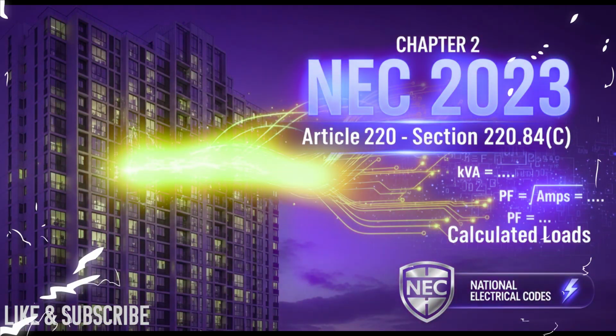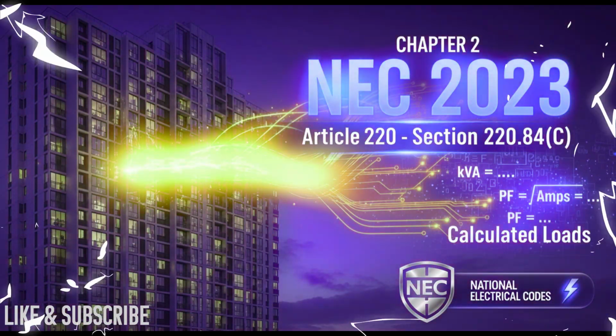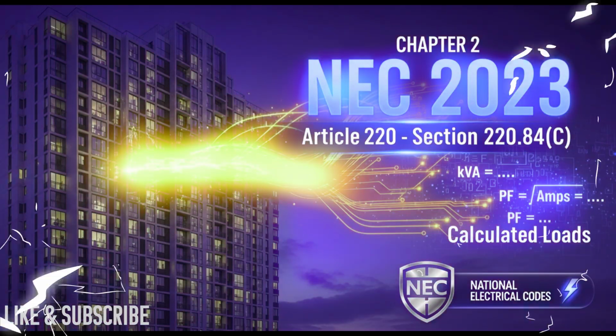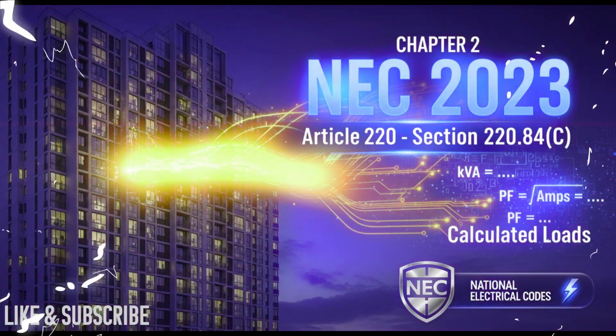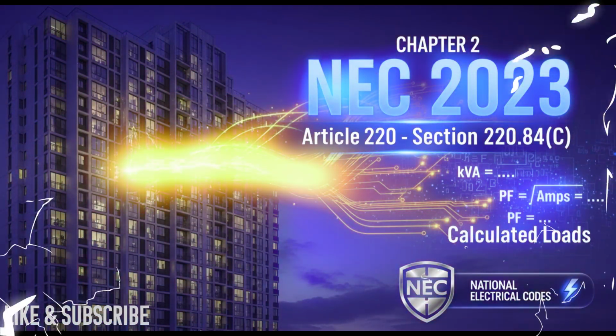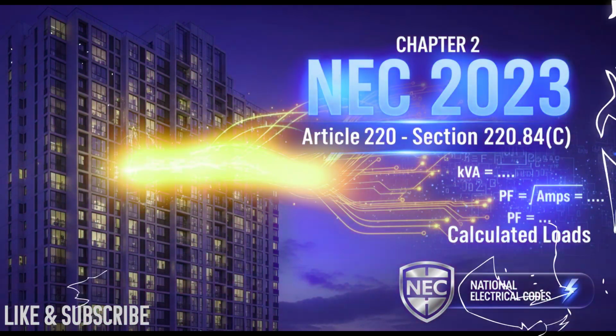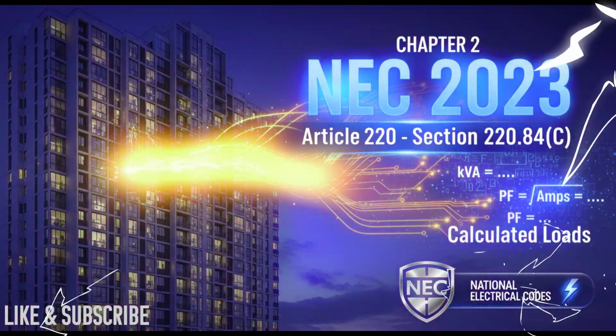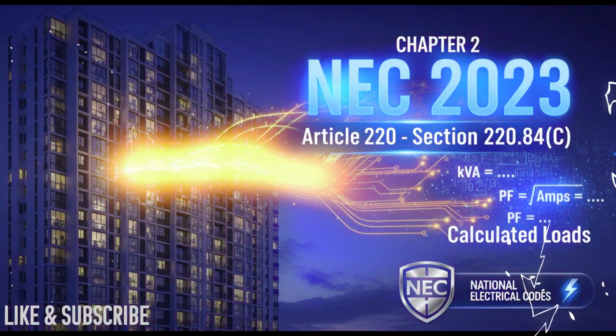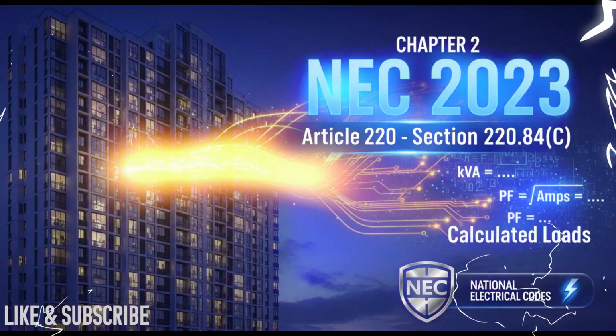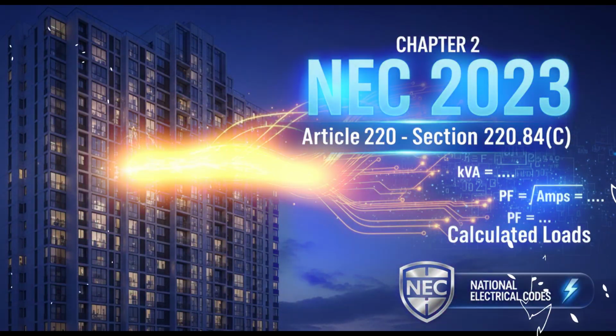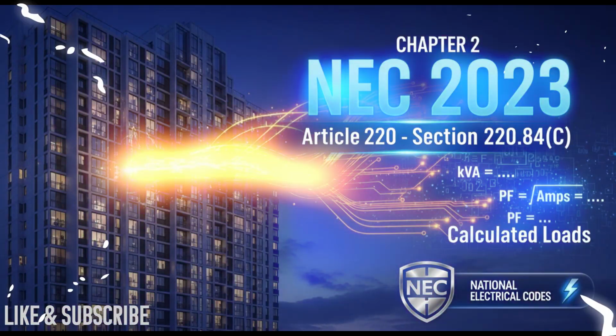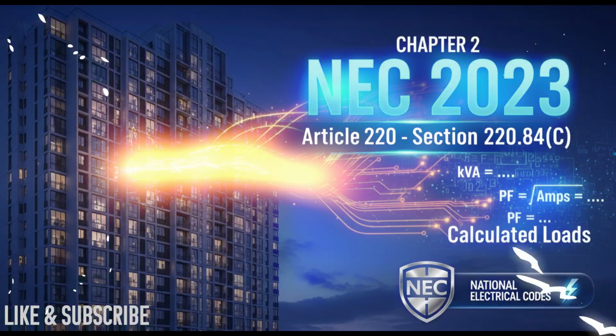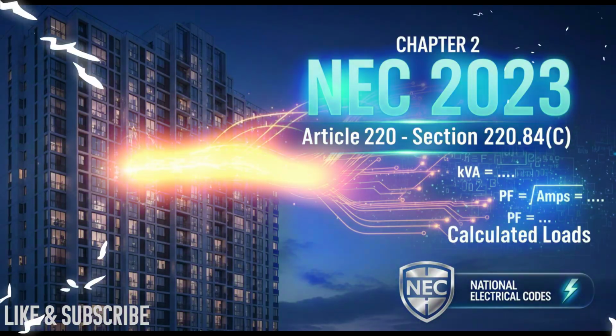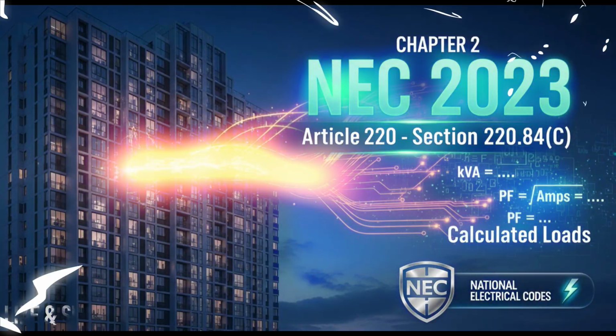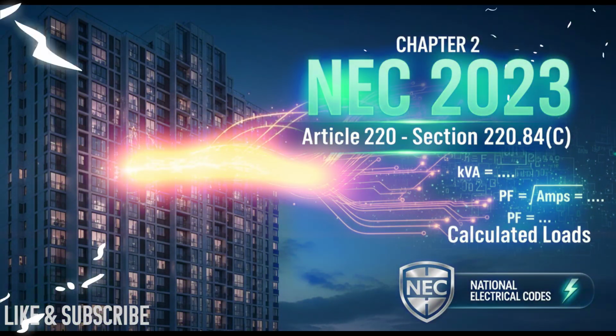Heating versus cooling. Now, this one seems a little different. You mentioned earlier it has a kind of built-in efficiency assumption, unlike the others. How does the code handle this? This is actually one of the clearest places where the code makes a rational and conservative assumption about how a building operates to prevent massive oversizing. Okay. The requirement is you only need to include the larger of the two loads, either the total air conditioning load or the total fixed electric space heating load, whichever one is bigger.